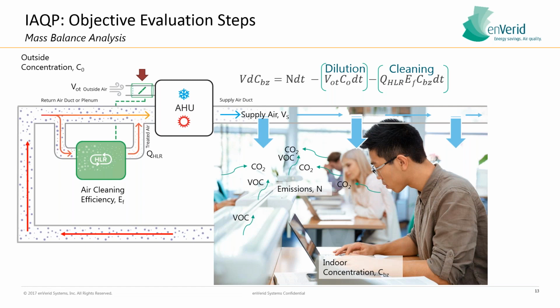Quantity of HLRs. HLR stands for HVAC load reduction device. You use a certain quantity of HLRs. You know the efficiency, EF, of those devices because you've done ASHRAE 145.2 testing on their ability to remove CO2, formaldehyde, and all the other VOCs. And then you've got CBZ, which is your indoor concentration. You set the concentration limit on each of these contaminants. And ASHRAE has actually published guidance as well as LEED. So if you're going for the LEED points, they publish what the maximum limits of formaldehyde or CO2 may be, for example. And that's how you figure out how much outside air you can actually reduce and how many air cleaner devices you need. Ted, pretty cool.